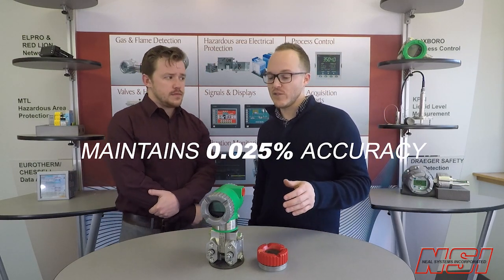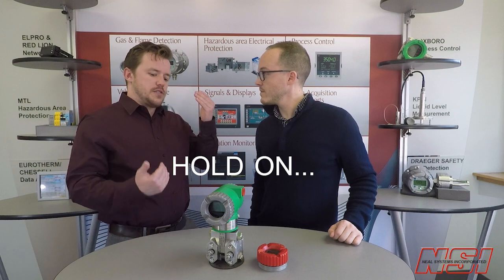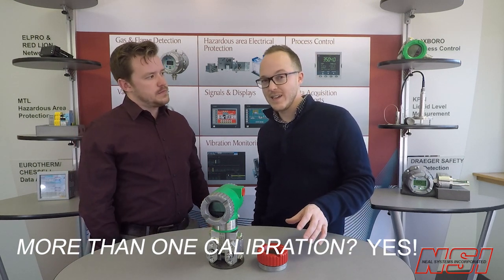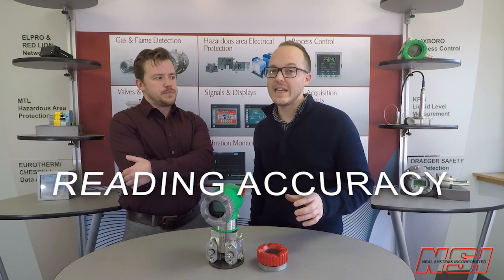Why is this going to let me skip that rule of thumb? With FoxCal technology, this pressure transmitter can maintain 0.025% accuracy from the high part of the range all the way down to the low part of the range. I know about large turndown ranges, but what you're telling me sounds like there's more than one calibration in that software. Well, there is more than one calibration, and all the calibrations stored in this transmitter seamlessly work together to give you what's called reading accuracy.